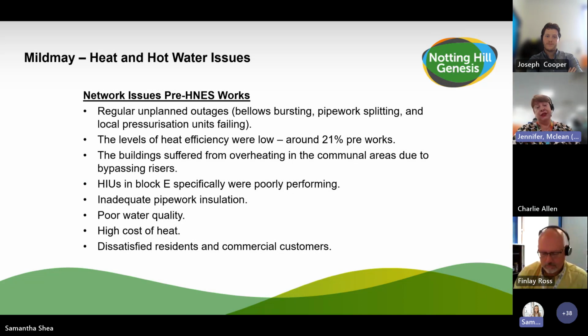One of the main issues we were experiencing was regular unplanned outages, including bellows popping all over the site, pipework splitting, and local pressurisation units failing. The level of heat efficiency across the plant was really very low, around 21% pre-works, and the buildings were suffering from overheating in communal areas due to bypassing risers.